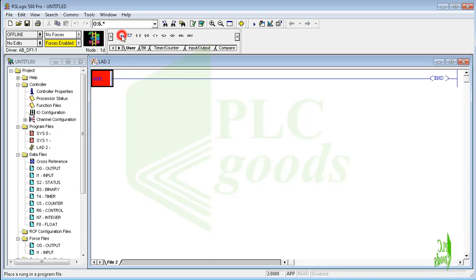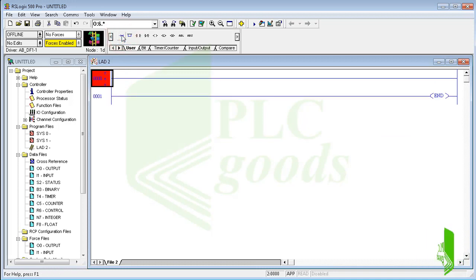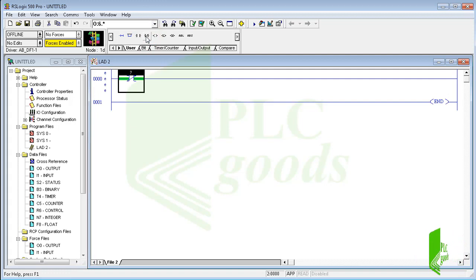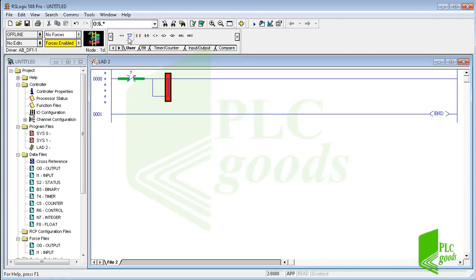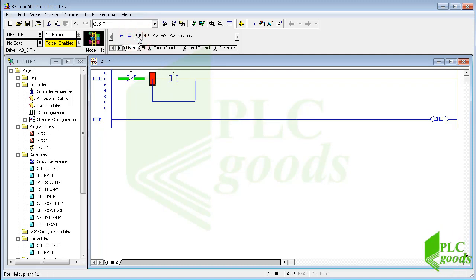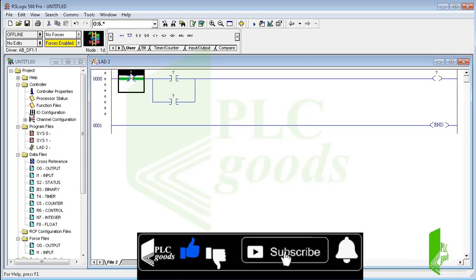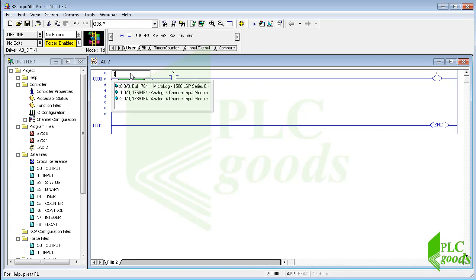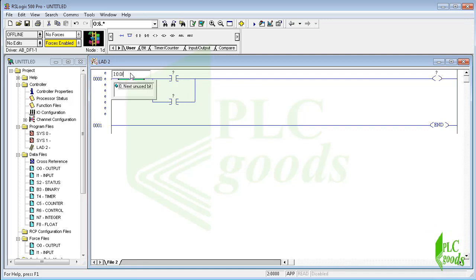Let me write my program. This instruction creates a new rung. Then I enter a normally closed contact. I also need a branch, and I use arrow keys to select where a normally open contact must be inserted. I click on the examine-on symbol to place a normally open contact as a holding contact. Finally, click on the energize output symbol. Now let me use the first digital input for this contact — its address starts with the letter I, its file number is 1, and I must determine the slot, word, and bit number. This contact will work like a stop push button.